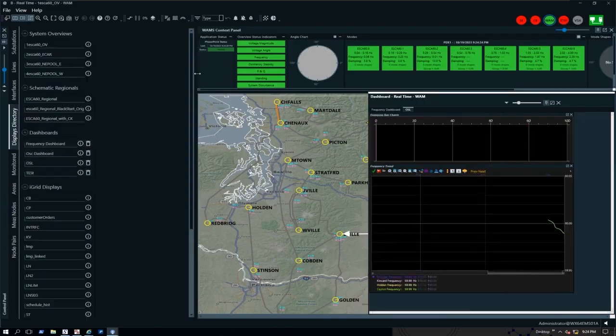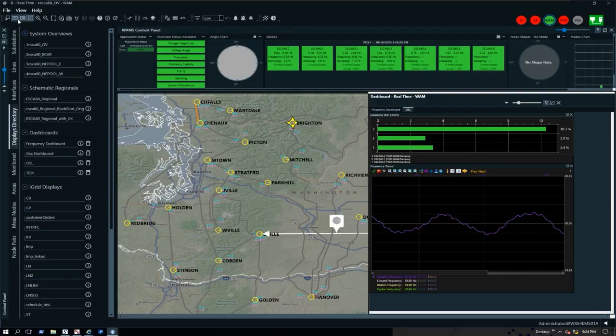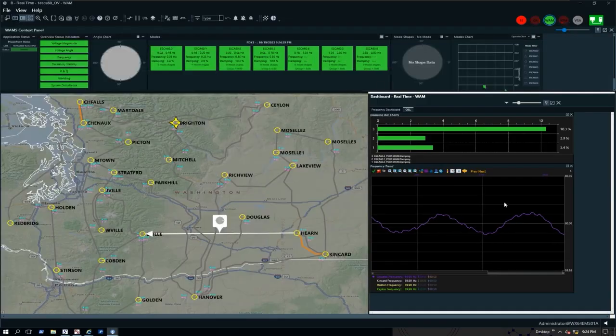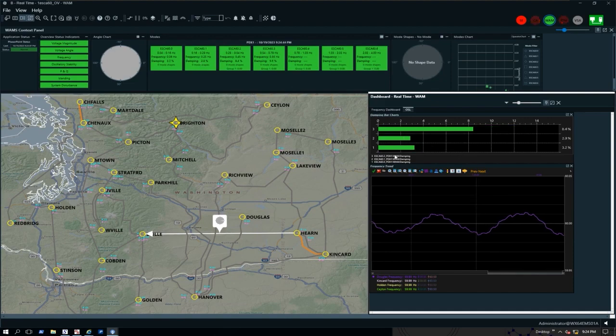So let me turn that on. I've already predefined a dashboard for that. Typically the oscillations are very small. I've got the damping modes for the first 3 oscillatory modes in a bar chart here at the top. If the damping, I believe, is above 20%, essentially we stop measuring it. So anytime you see the damping drop off here, when the damping is very high, the oscillations are going to be immediately squelched out. So we typically don't show very high damping above 20%.